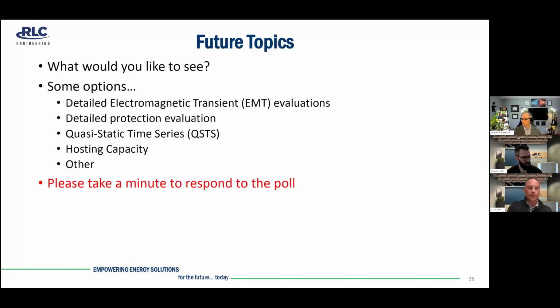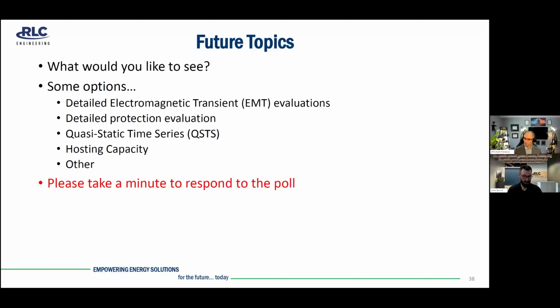Yeah, I'll snag that one as well. Typically what we aim to do is have good manufacturer contacts, and that can take a few iterations to get the person that's in charge of updating the inverter models and is responsive. That's usually our first path if we can reach directly out to them, and sometimes we'll need to loop the utilities in to make sure everybody has visibility. But if that's not an option, then sometimes we'll put the onus back on the developers to reach out to the manufacturer they're purchasing the inverters from. But in general, reaching out to manufacturers directly works very well.